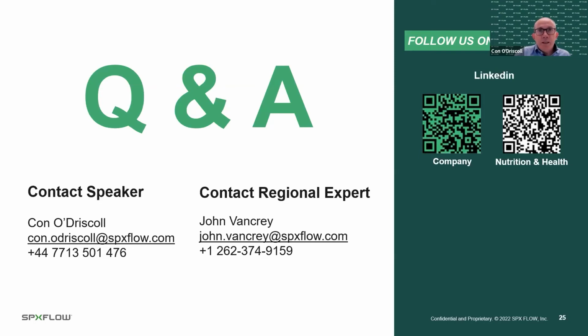Let me see here. Yeah, we talked about utilities. Oh yes, so a good question on the ROI and whether the electrical consumption is factored in. Yes, it is. So the consumption is based really on running the pump, and the instruments obviously won't require a lot of consumption, and the UV lamps. So the consumption, from memory, is in the range of less than half a kilowatt. I need to double check that, but that's the range that we're looking at. But it is factored into the ROI. Thank you.